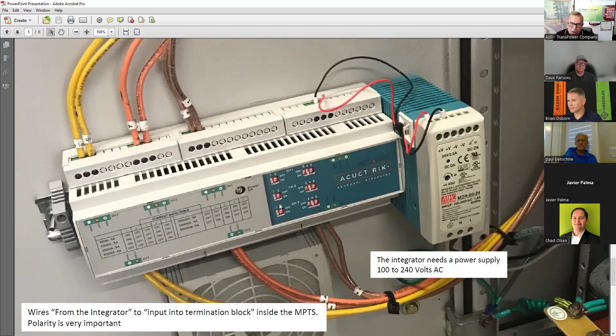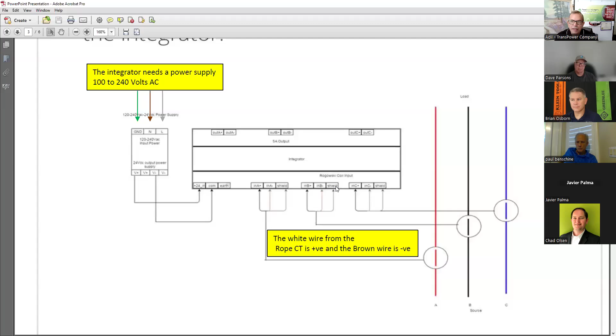All right. So one more thing here that you need to notice, we use Rogowski coils so that you don't have to keep buying CTs again and again, because then it becomes very expensive, right? These CTs can get very expensive. You went and bought some CTs and they were wrong. That's why you use Rogowski coils, and that is why it is bundled.